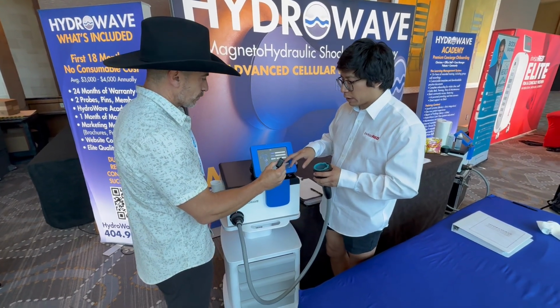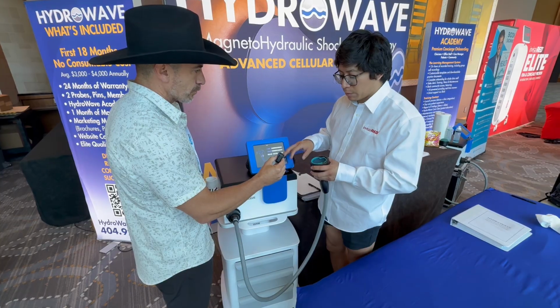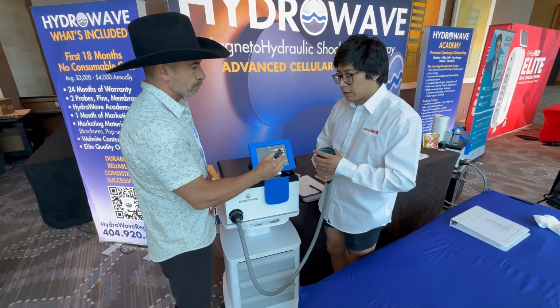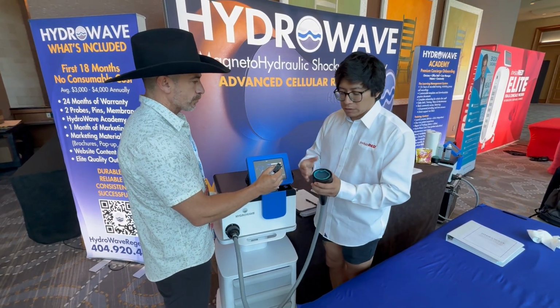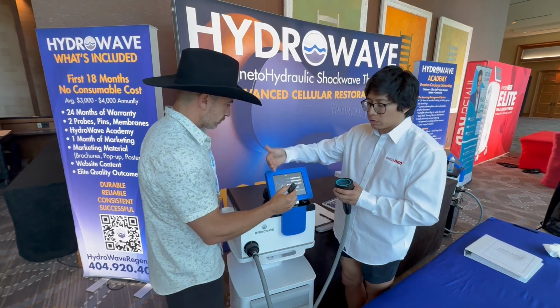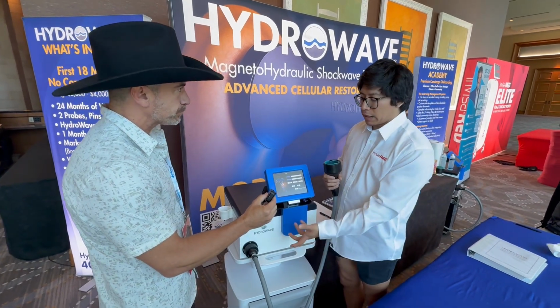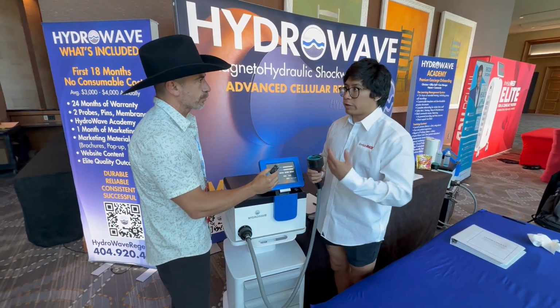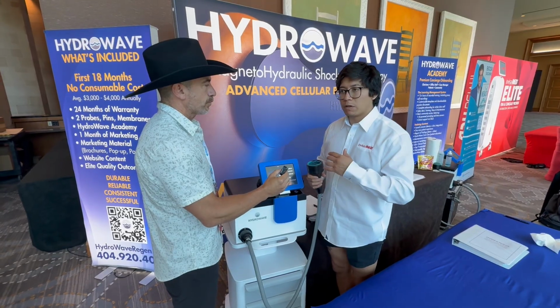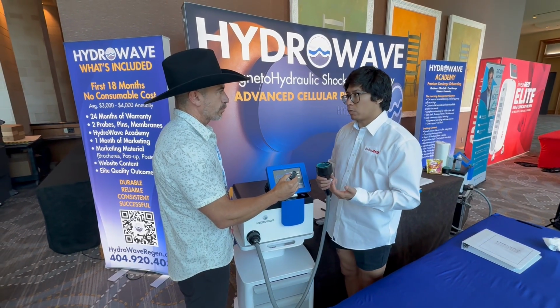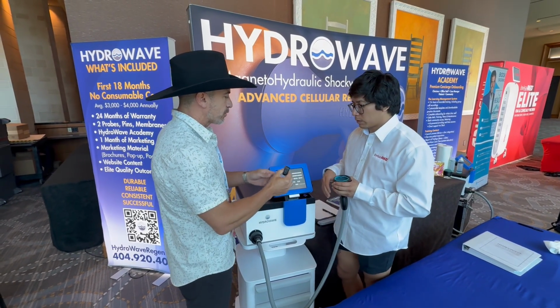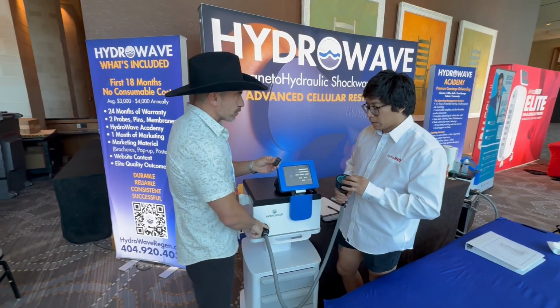If you do drain the head, what I'd suggest is every Monday, go ahead and drain the water out. Since the water is already drained from the membrane, you'd be able to disconnect it and connect our applicator so you can drain the head and then fill it back in with new distilled water.